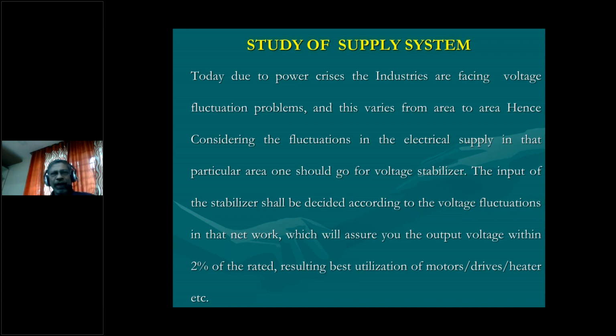So the selection of proper equipment is also very important. In this situation, we always recommend going for the unbalanced type voltage stabilizer. Now, there are some UPS in some systems. You need only stabilizers, but you do not require a UPS. Suppose in case of interruptions, you can restart the machines. Here we come to some practical problems. Let us take an example: your input voltage comes to, say, 380 volts and your output voltage is 415. So from 380 to 415 you are getting balanced 415 volts from the stabilizer. So what is the boost voltage? It is 380 to 415, so 35 volts are boosted by your stabilizer and you are getting balanced voltage.